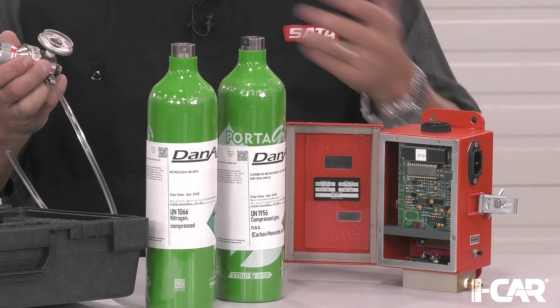It was off by 1, so we adjusted it from 49 to 50. Then we disconnect it from the CO bottle and hook it up to the nitrogen bottle to clear all the CO out of the sensor. You do want to shut off the air before calibration, so we shut the air valve off, bled the air out of the system, did the calibration, then turned the air back on, and it went right back to 0. Yours fluctuates between 0 and 2 parts per million, which is perfect.